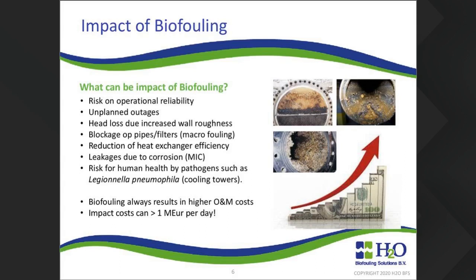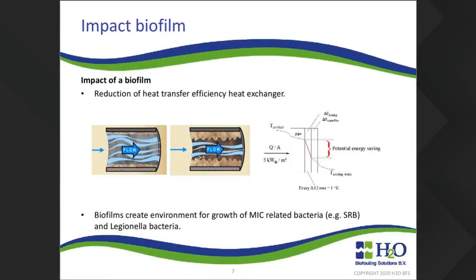Now, biofouling always results in higher operation and maintenance costs due to the damage or due to the fact it's a fouled system. The impact can go up to more than 1 million euros per day in a circumstance where there is an unplanned shutdown of the plant. An example of the impact of a biofilm on the heat transfer rate at a heat exchanger: a biofilm of 0.12 millimeter will already result in a decrease in heat transfer efficiency of more or less 1 Kelvin. So it has a high impact on the energy which is required to cool the processes. As mentioned, the biofilm layer is a perfect habitat for MIC bacteria like sulfur-reducing bacteria, but also the Legionella bacteria.